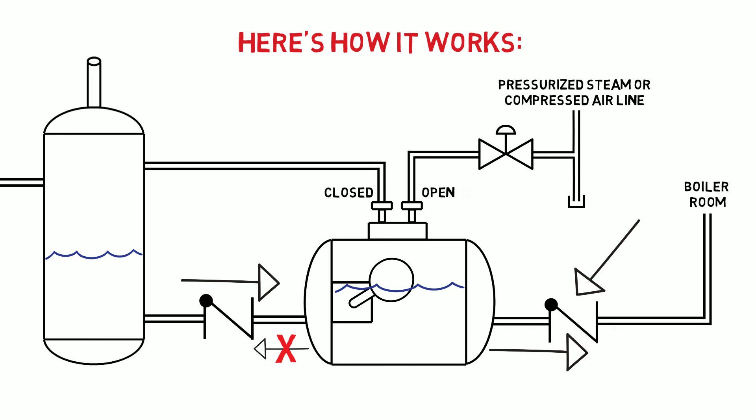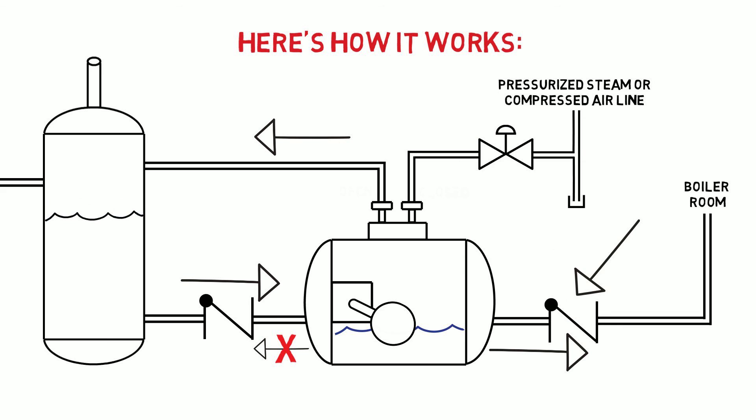While the condensate is being pumped, the liquid level in the tank starts rising from incoming condensate. Once the level in the pump is up towards the top, the internal mechanism closes the motive valve and opens up the vent valve. The pressure inside the pump vents back to the tank and the process starts over, filling the pump.